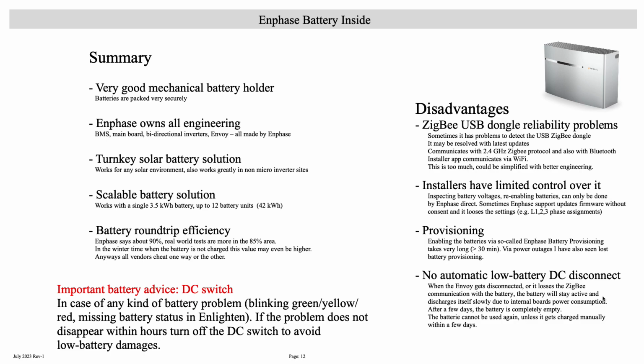After a couple of days or a week it's very, very low, and then it starts dying. What's needed is a kind of automatic DC disconnect when the battery voltage goes below 2.5 volts per cell, or together below 50 volts. This is not the case, but there is a solution: turn off the DC switch.